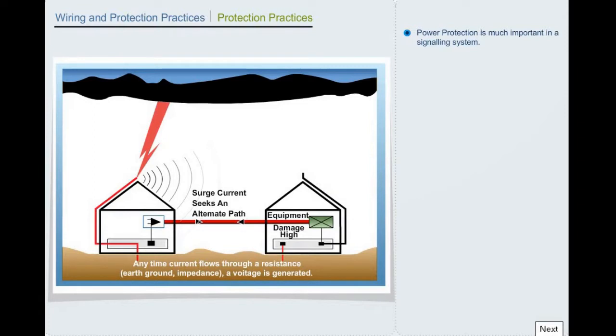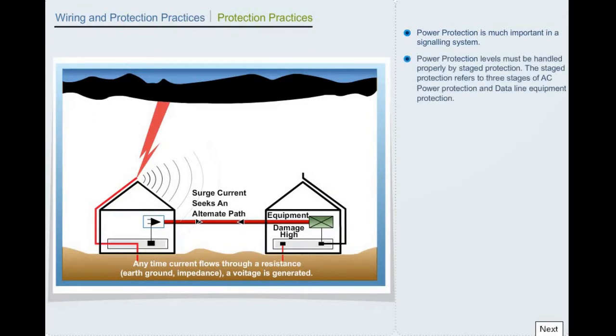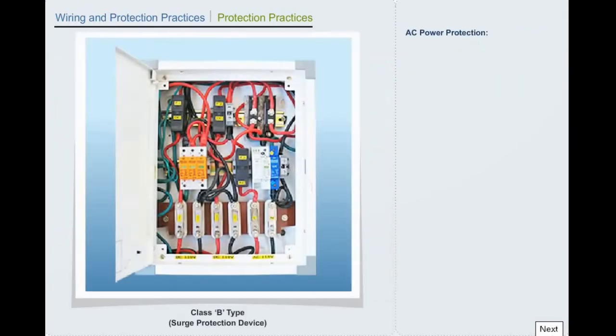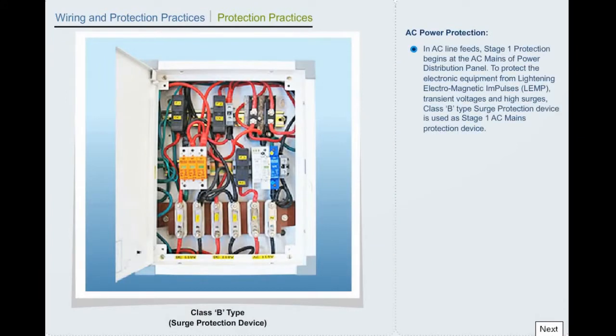Power protection is much important in a signaling system. Power protection levels must be handled properly by staged protection. The staged protection refers to 3 stages of AC power protection and data line equipment protection. In AC line feeds, Stage 1 protection begins at the AC mains of power distribution panel.